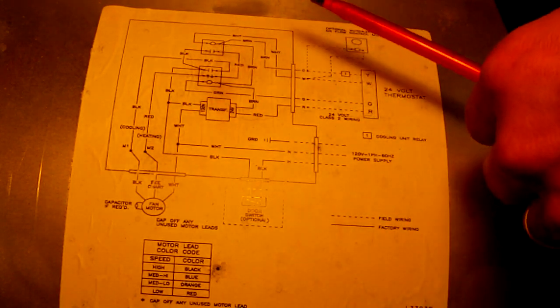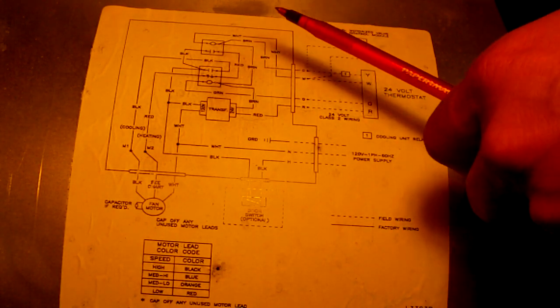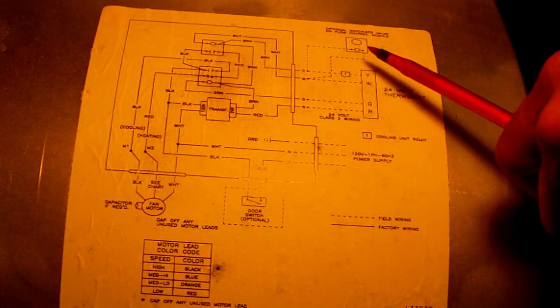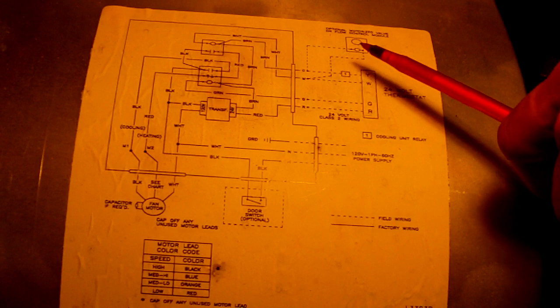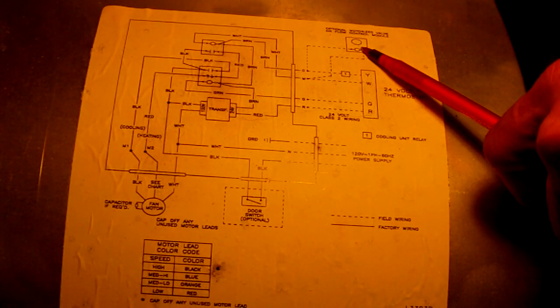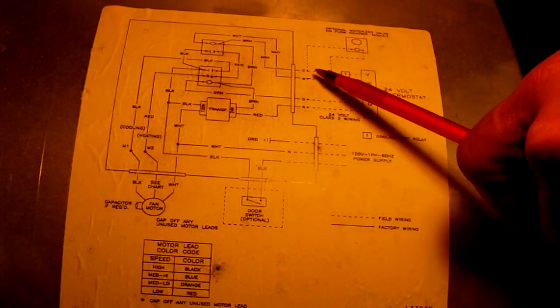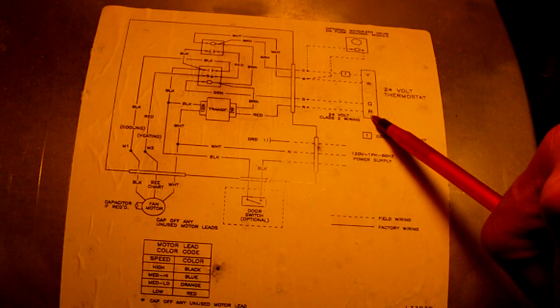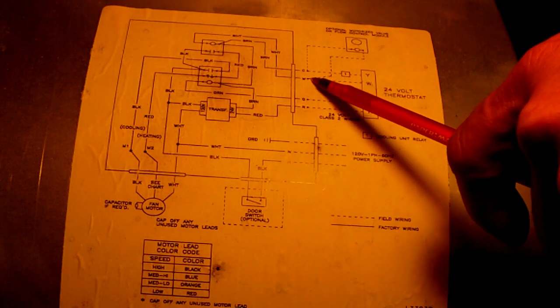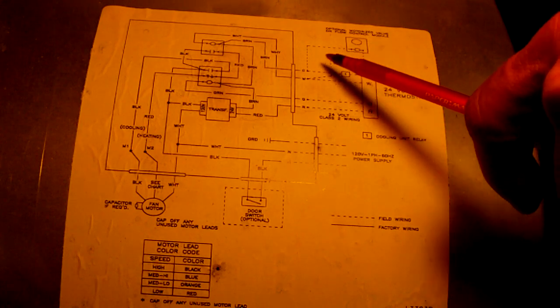Now, this is a hydronic system - we don't have strip heat or anything like that. The hydronic needs the pump so it can pump the water around through the radiator. It's like a radiator inside the air handler on the other side - the hydronic. At the same time that we powered W for call for heat, we have to run this wire to the pump over here - W.